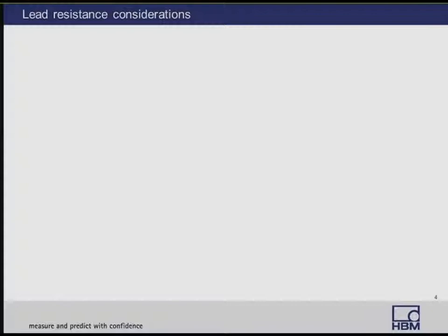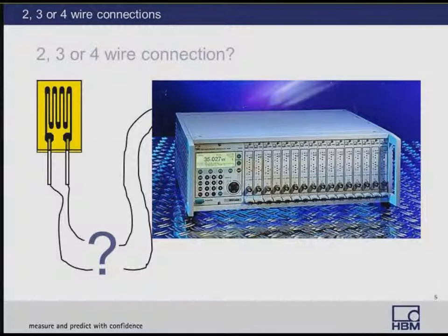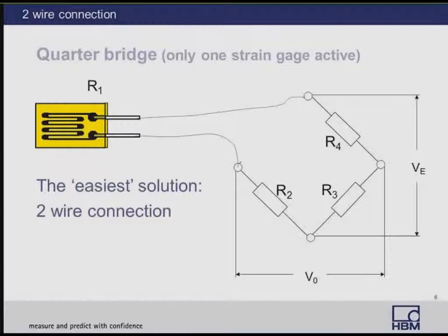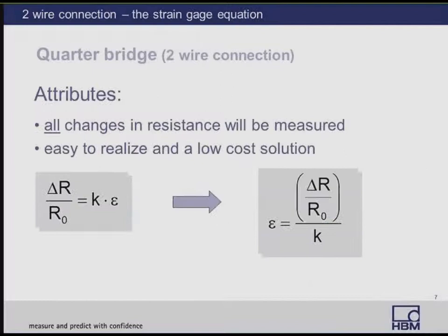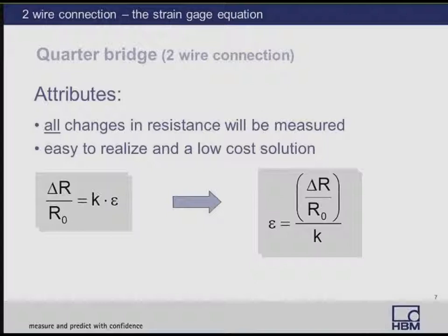When making a strain gauge measurement, which should you use: two-wire, three-wire, or four-wire? The easiest solution is a two-wire connection into the Wheatstone bridge. With a two-wire connection, all changes in resistance will be measured. It's easy to connect and the lowest cost solution. The standard strain gauge equation finds that the relative change of resistance is proportional to the strain applied. The gauge factor K is expressed as the ratio of relative change of resistance to strain: ΔR/R = K × ε, or equivalently, ε = (ΔR/R) / K.